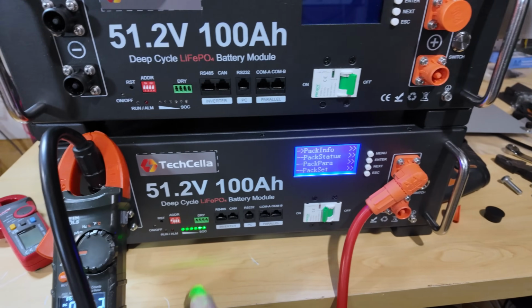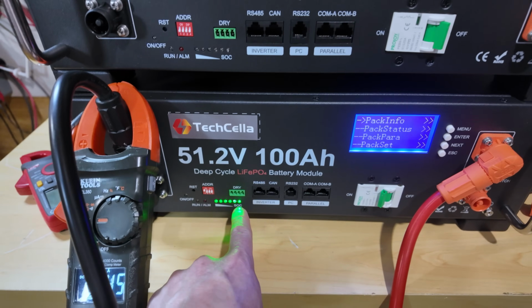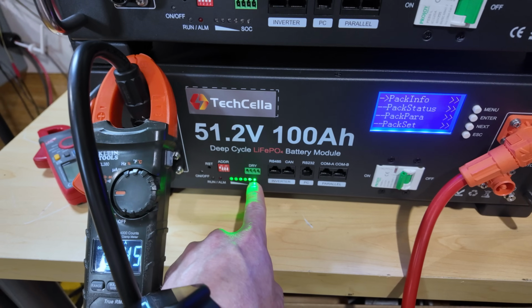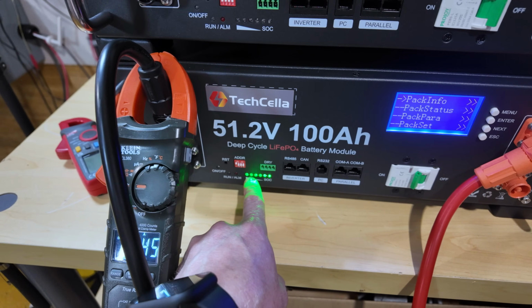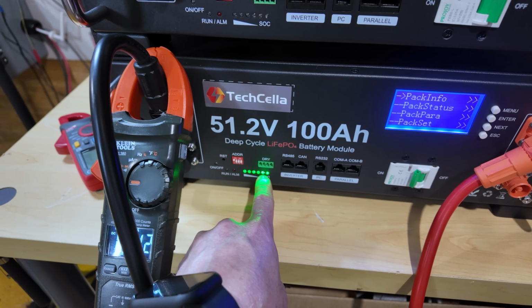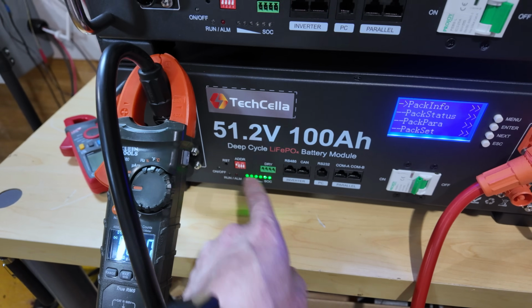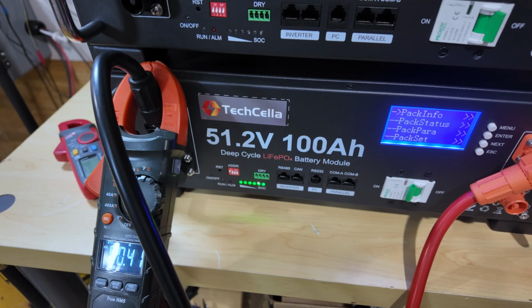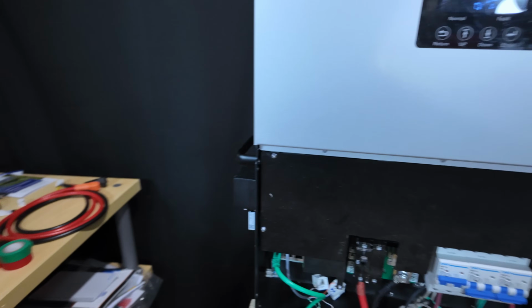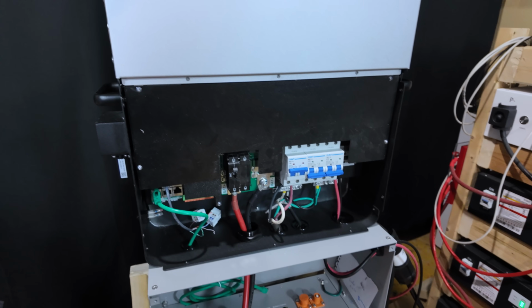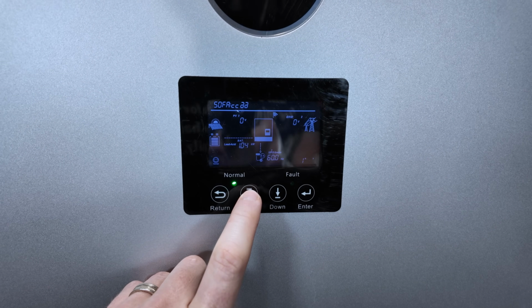And really with a lot of these, the pre-charge cycle actually runs when you watch these LEDs light up. So you'll watch it kind of walk through each indicator light. That's when your pre-charge is actually occurring. So at the moment, no communications between the battery and the inverter. We'll come over here, turn on the inverter itself, and then our fans start kicking up.